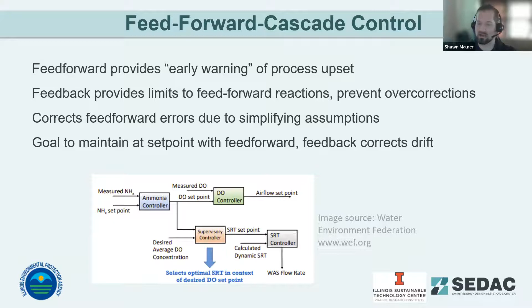Digging into a bit more of how that kind of AI system works, artificial intelligence software uses real-time operational data compared to historic data in your plant. It's one method of using AI. If you have good SCADA trends and historical data, a programmer will build out a model, and your AI logic will look at that as a digital twin of your plant. You have historical data showing how your plant reacted in the past to different upsets, so it has a history of how the system works. Then you have a model of optimized control, how it should work based on idealized processes. It compares those two, and the difference is used to generate how your plant will react to that data.